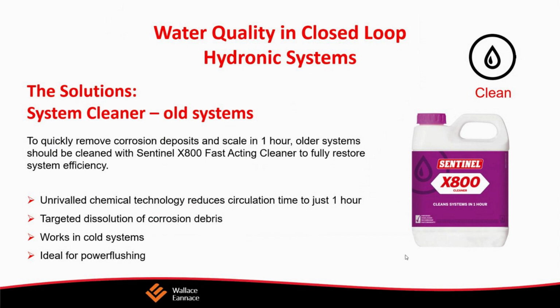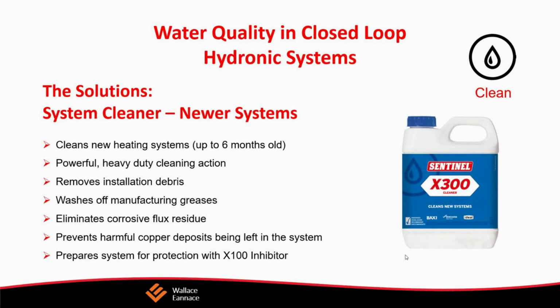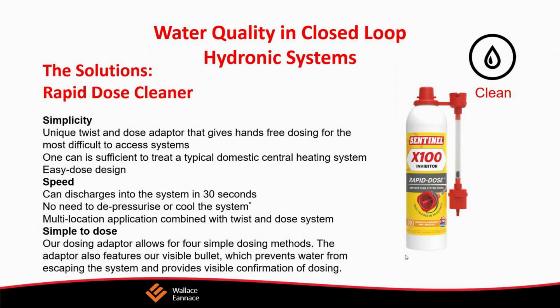We don't take it so seriously, but when you go to Europe, for example, the requirement for water treatment is so critical. This is right out of a European boiler manufacturer's installation and operation manual: all recirculatory water systems are subject to corrosion unless water treatment is applied. What's really interesting is it says you must add a suitable inhibitor to the systems, and all systems must first be flushed, and a suitable inhibitor must be added. And then failure to flush and add inhibitor to the system will invalidate the appliance warranty. So a boiler's warranty in Europe is no longer valid if you do not flush and inhibit the system.